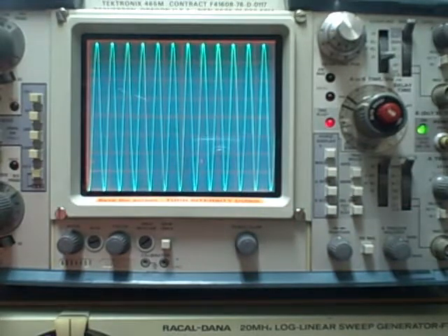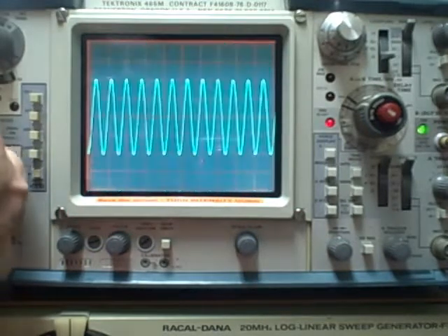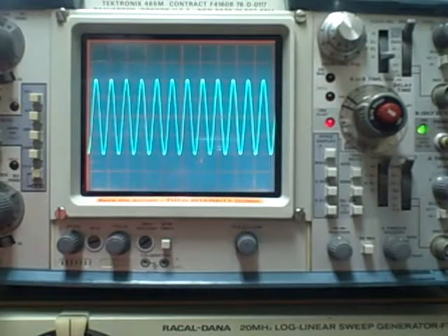Let's go ahead and progress to the next range setting, which would be 20 millivolts per division. We see now that we are at half scale, which is to be expected, because we just went from 10 to 20 millivolts per division. So we doubled our requirements, and therefore pulled ourselves down to half scale. At 20 millivolts per division, 4 divisions, that would be 80 millivolts required.